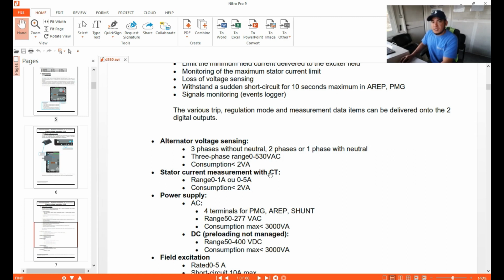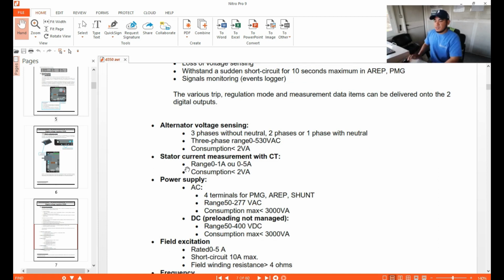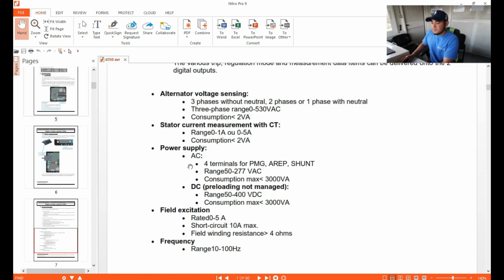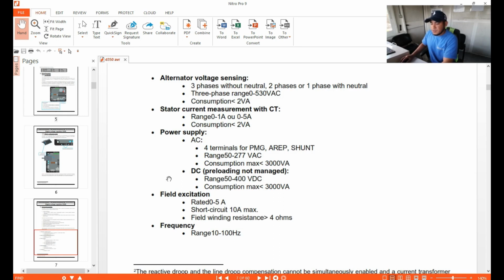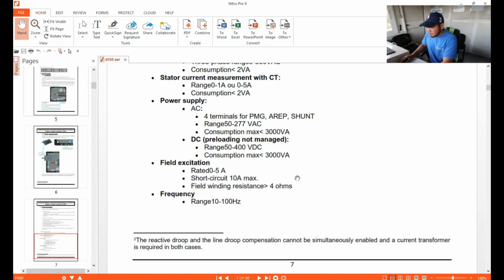Stator currents are measured with the CT, range 2. You can use 0 to 1 amps, and you can also use 0 to 5 amps. This is the standard CT you can use, and it has a consumption of 2 volt amperes. Power supply AC, the 4 terminals for PMG, AREP, and shunt can range from 50 to 277 volts AC. The maximum consumption is 3000 volt amperes. DC input not managed, range of 50 to 400 VDC. Consumption is 3000. So this one is okay.